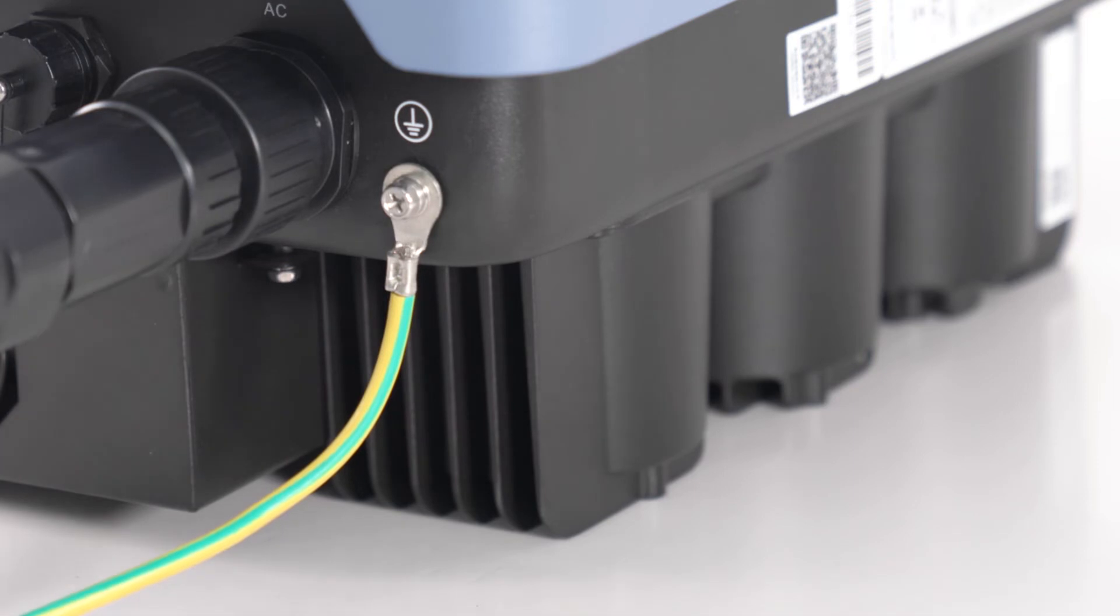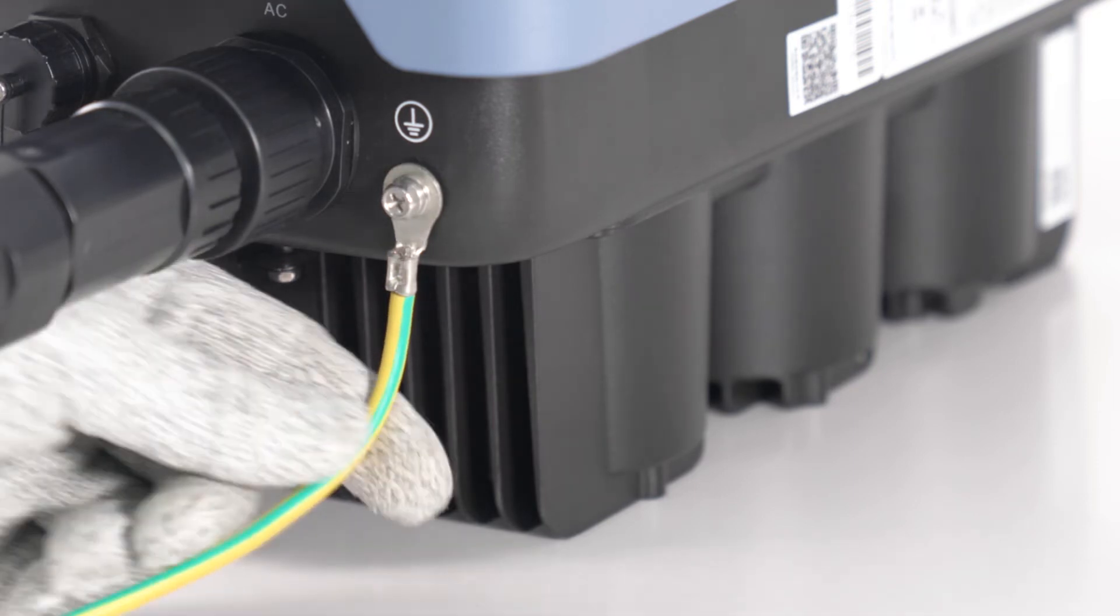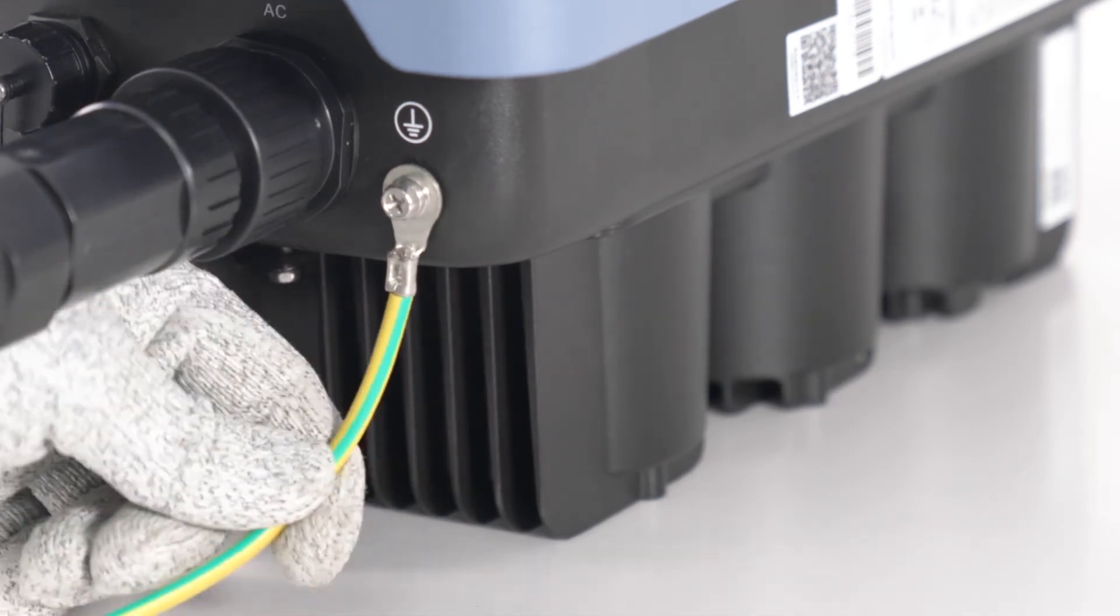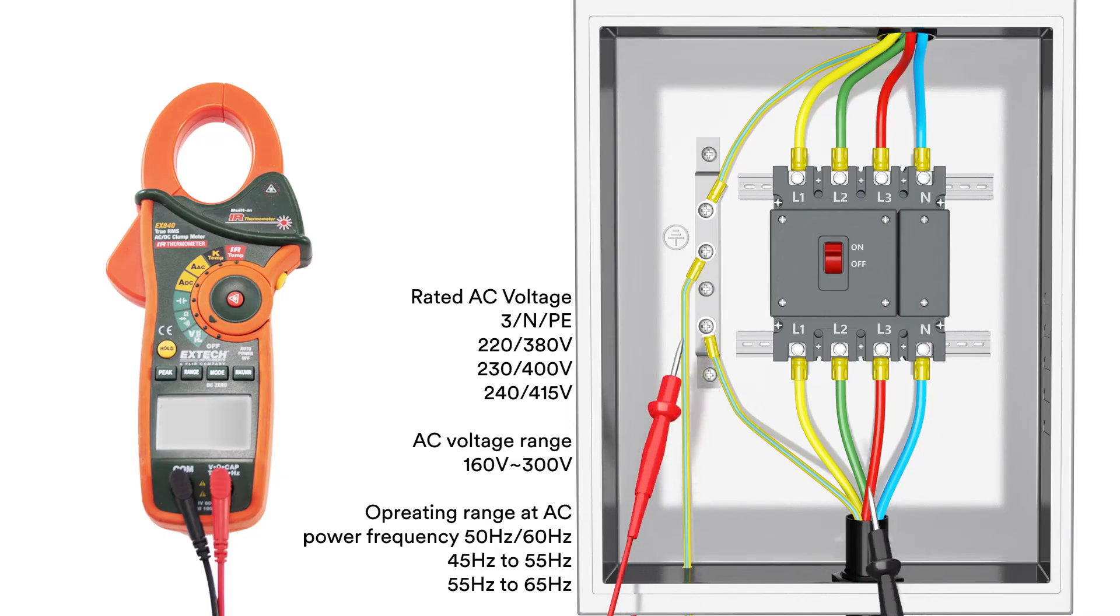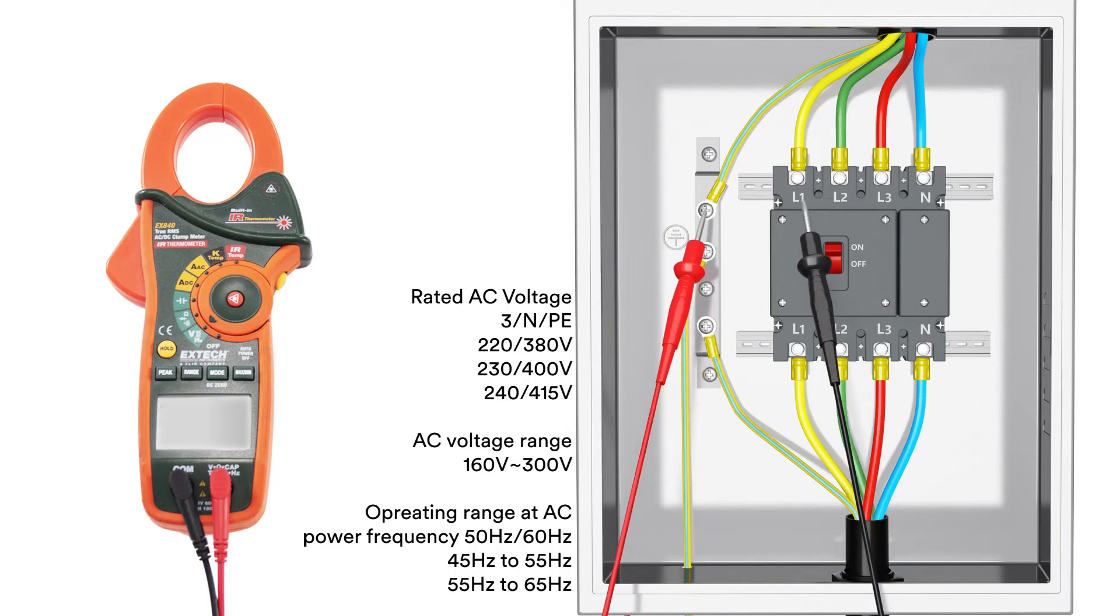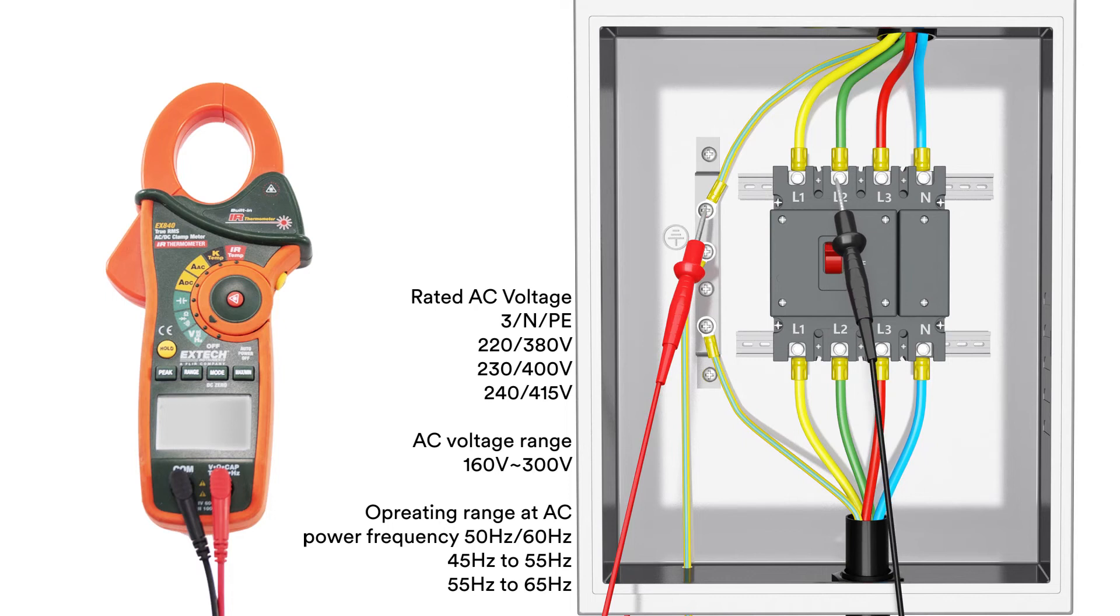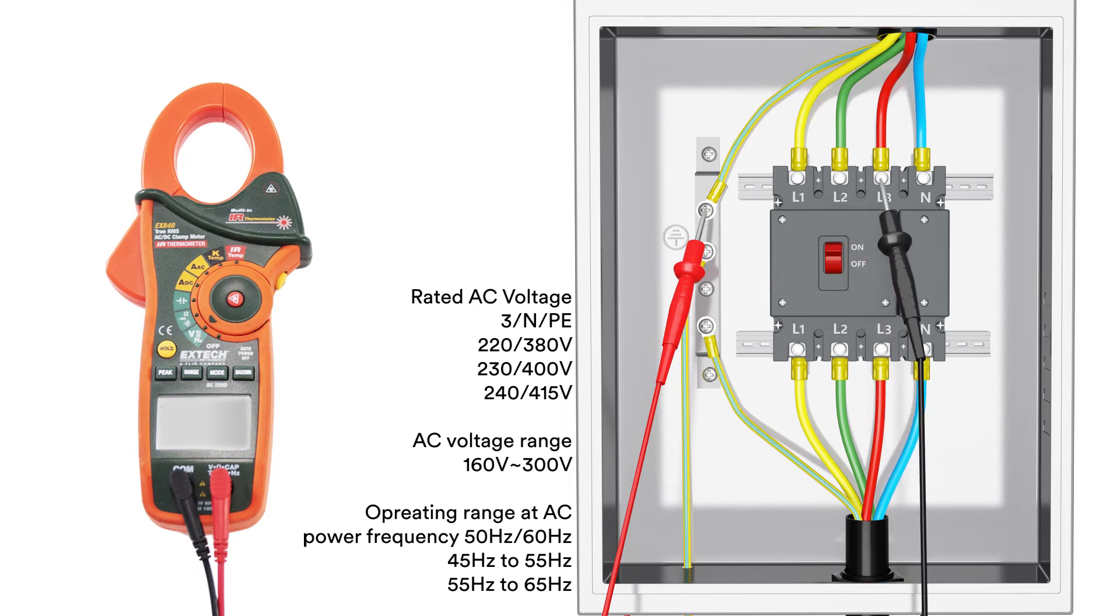Check the PE connection with a multimeter. Make sure that the inverter's exposed metal surface has a ground connection. Check the grid voltage. Check that the grid voltage at the point of connection of the inverter complies with the permitted value.